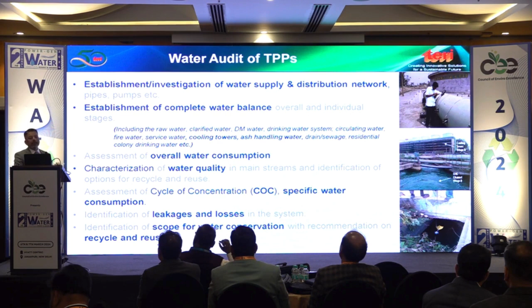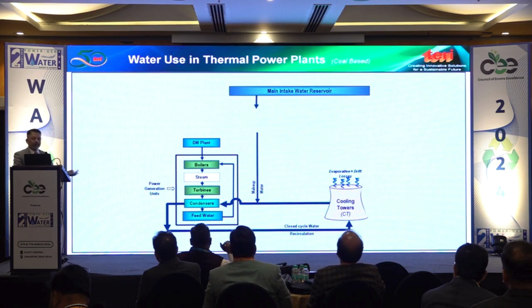I don't need to explain the process in detail, but in this context, we use steam to generate power. That steam comes in a closed cycle from a boiler, which uses water through the DM plant. When we do condensation, the steam has to be condensed using cold water. That water is largely used in a closed circulation system, with evaporative and drift losses requiring makeup water from a fresh water source, usually a river or a combination of river and groundwater. After treating this water, it's used for the DM plant, for makeup to the closed circulation system, and for other uses like township and ash handling.